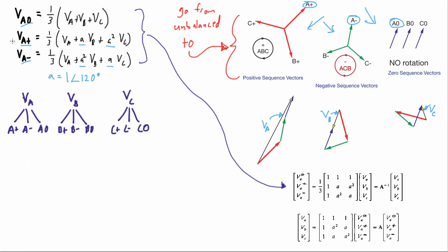Now it's interesting to notice that these 3 formulas at the top can be represented in these connective lines that you see here. So in the A positive sequence, that connection from the unbalanced phasor to the component phasor can be shown in that formula. The negative sequence can be shown and the zero sequence can be shown. So they all match up. Now our variables that we're using in this instance are all for the A phasor. Now all we have to do is switch them over to the B phasor and we get that second cluster of 3, and the C phasor, the third cluster of 3.